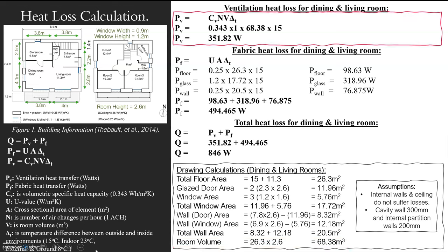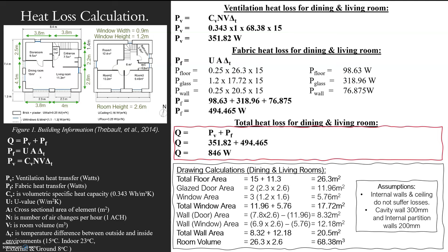Once I've got all that information, I literally plug it in — it's as simple as that. Cv is my specific heat capacity, N is my number of air changes, volume I've determined, and my temperature difference between outside and inside. Lovely — I can just plug that in. For fabric, I've got my U-values for three different elements: my floor, my glass, and my wall. I separate them out, I've got the area for each, and I've got the temperature difference between each element and outside. I get my fabric heat loss and then add them all together.